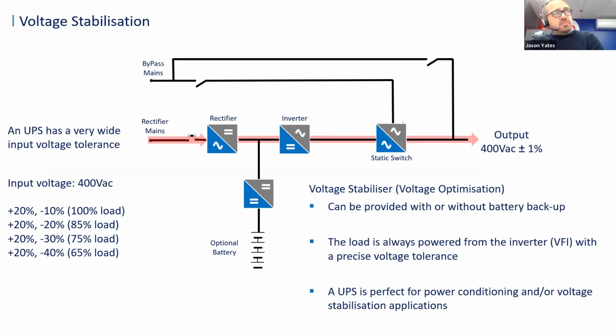Another function of UPS is the UPS as a voltage stabilizer. Sometimes people refer to this as voltage optimization. I don't know if you're familiar with an online UPS system, but that is a typical diagram of an online dual conversion UPS. We call it dual conversion because the main supply comes in, we convert the AC to DC, that's our first conversion, and then we reinvert the DC back to AC again, and that's our second conversion, hence the term dual conversion.